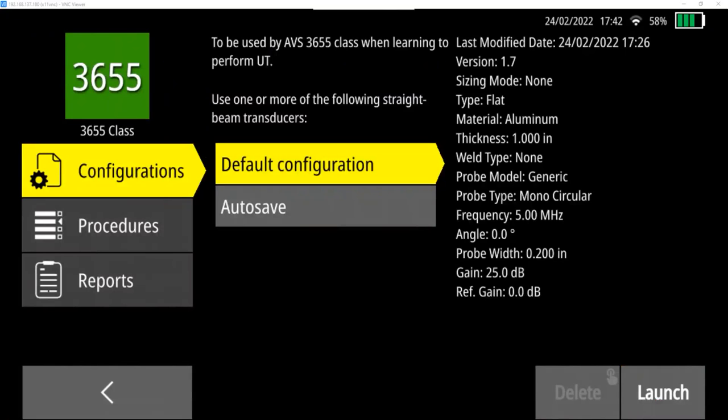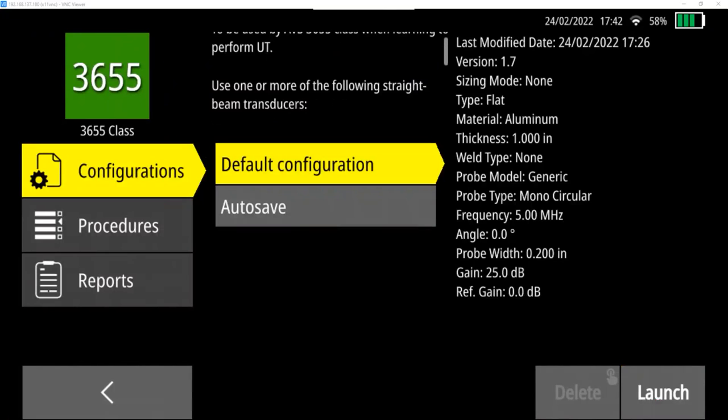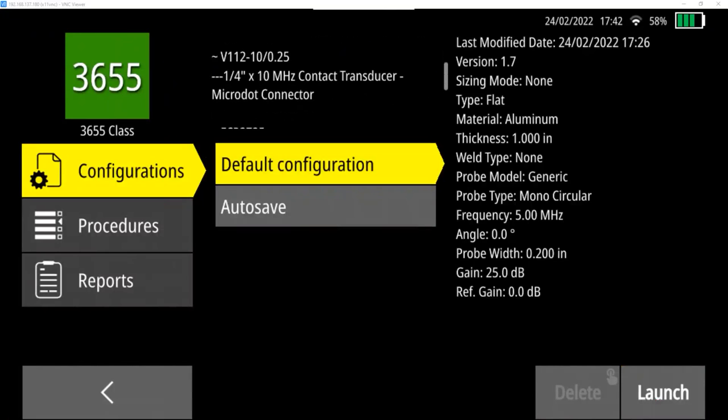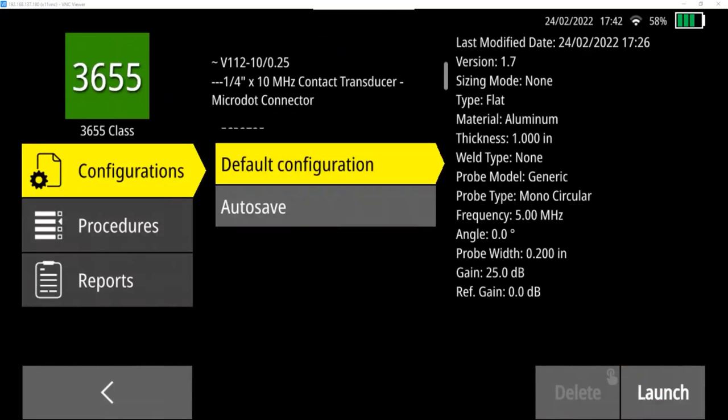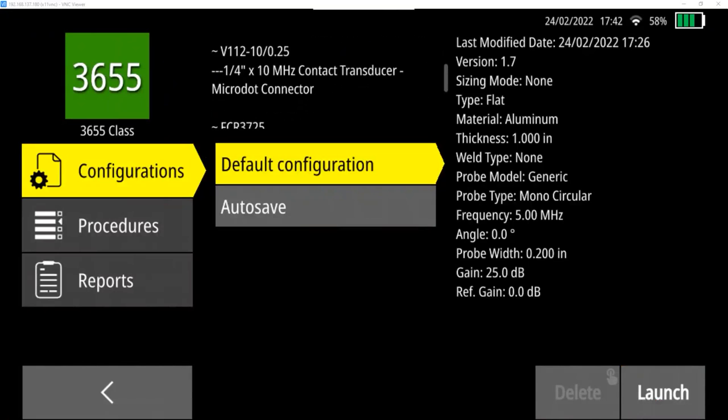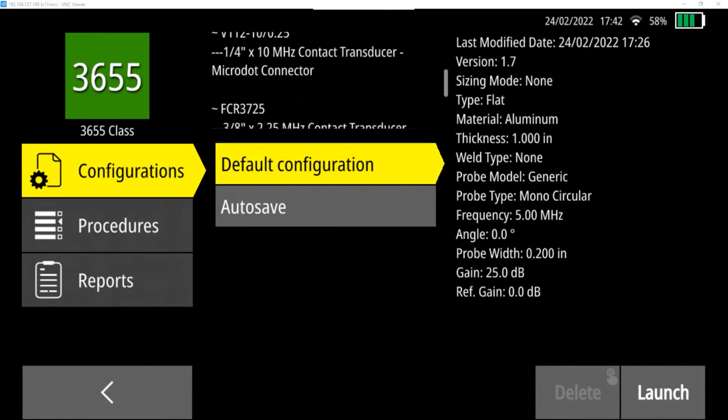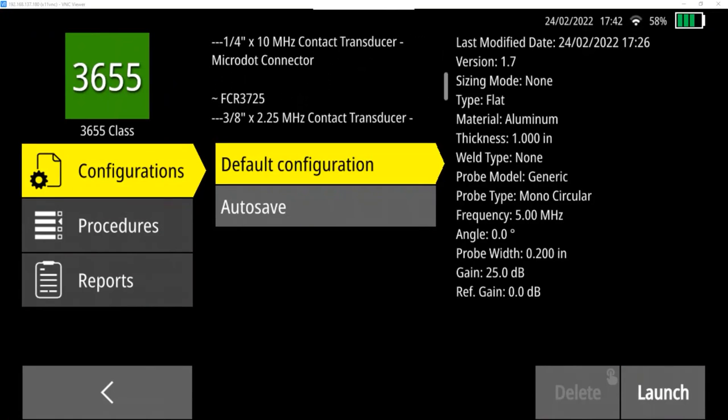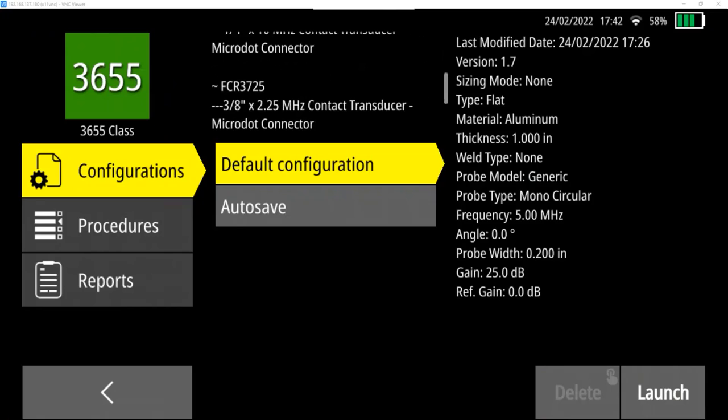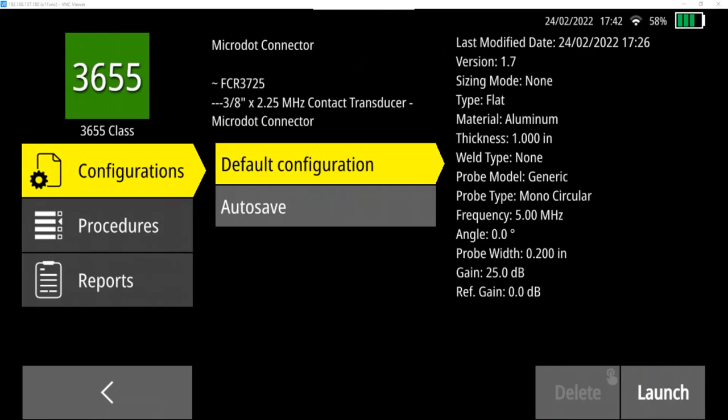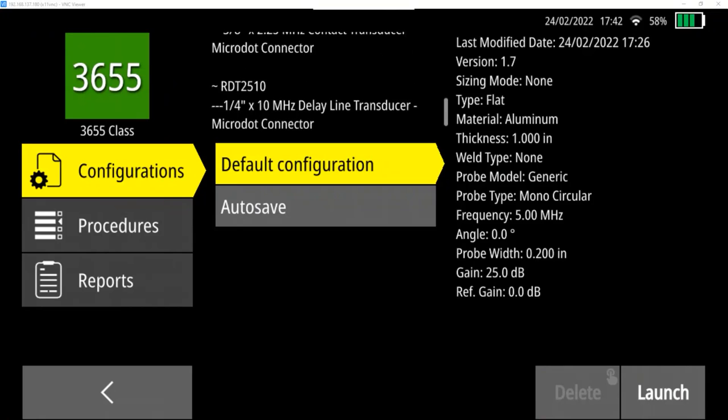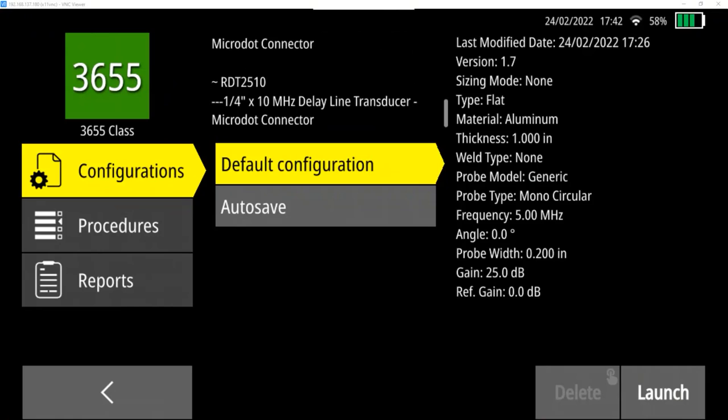So this is to be used by the AVS3655 class when learning to perform ultrasonic tests. You can use one or more of the straight beam transducers that are available, the first one being the model V112-10-0.25. That's a quarter-inch, 10 megahertz contact transducer with a micro dot connector.